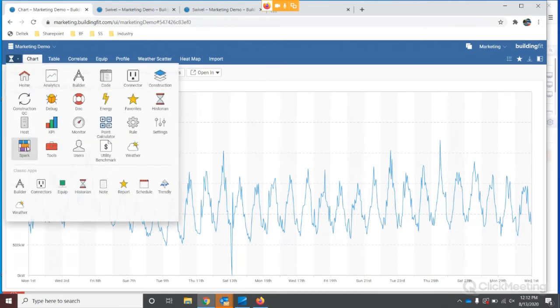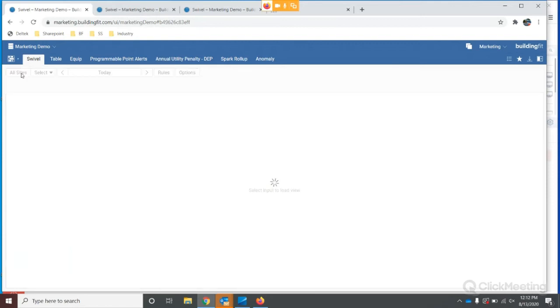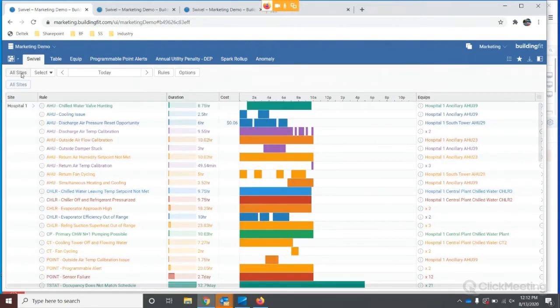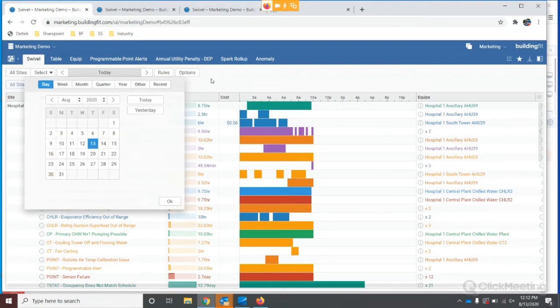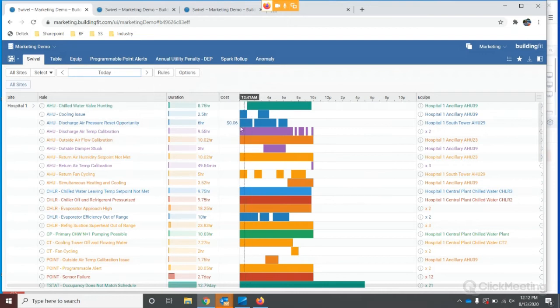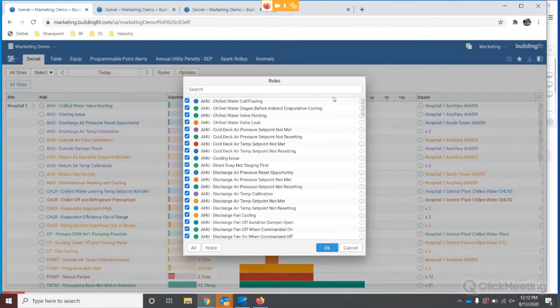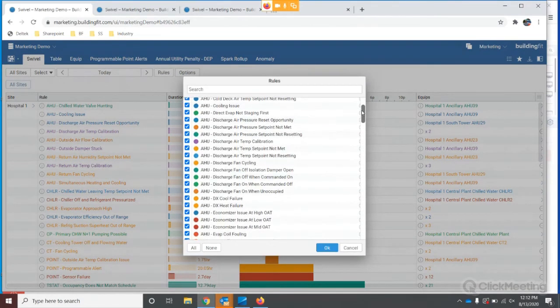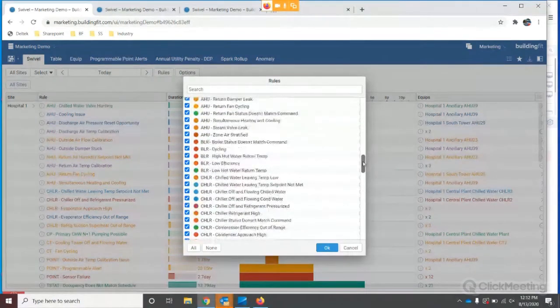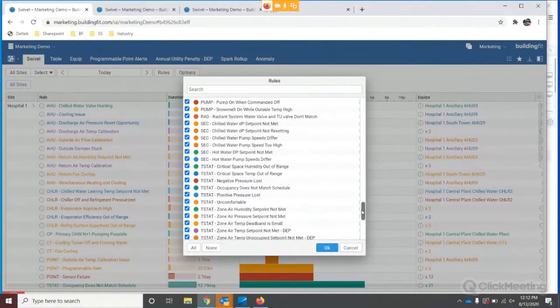Now, from a fault detection perspective, the analytics engine for SkySpark is where we've put a lot of our development time over the past 7 years developing rules. We're looking at an entire site here of all the rules being triggered on a given day. We've built and tuned 200+ rules, and I'm flying through this list—air handlers, chillers, boilers, pumps, thermostats, and terminal units. We'll really focus on terminal units with KPIs here in a bit.